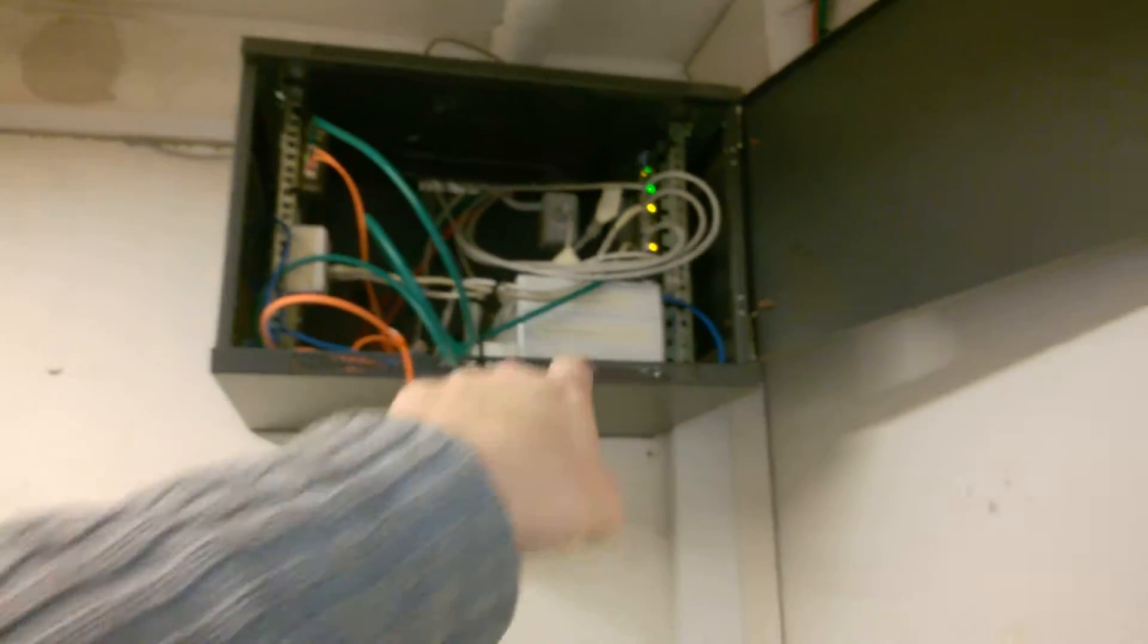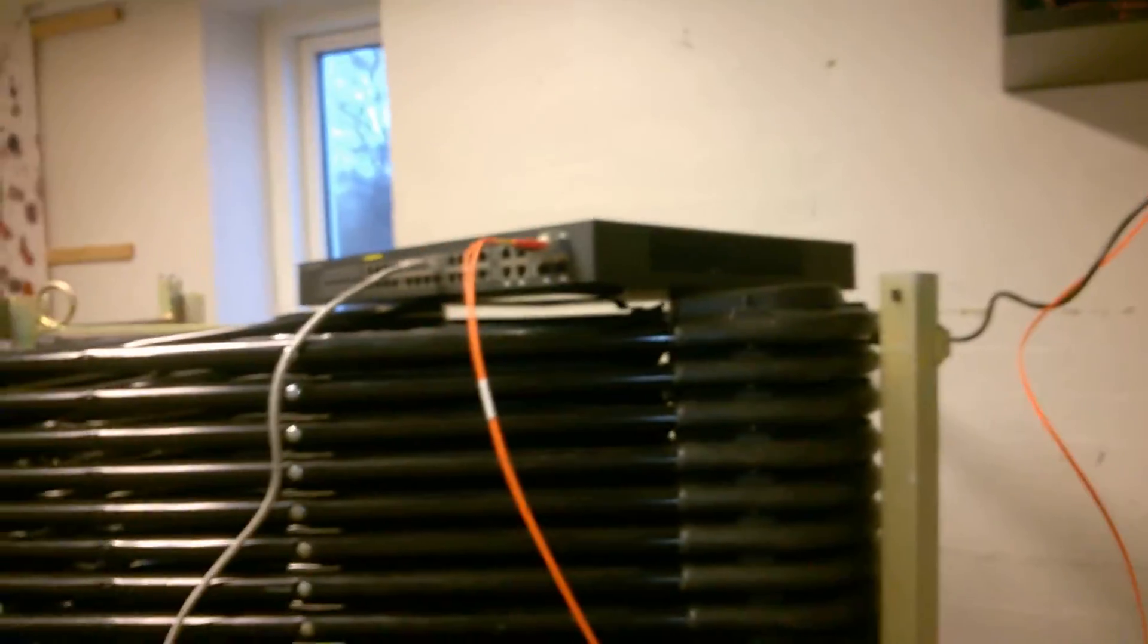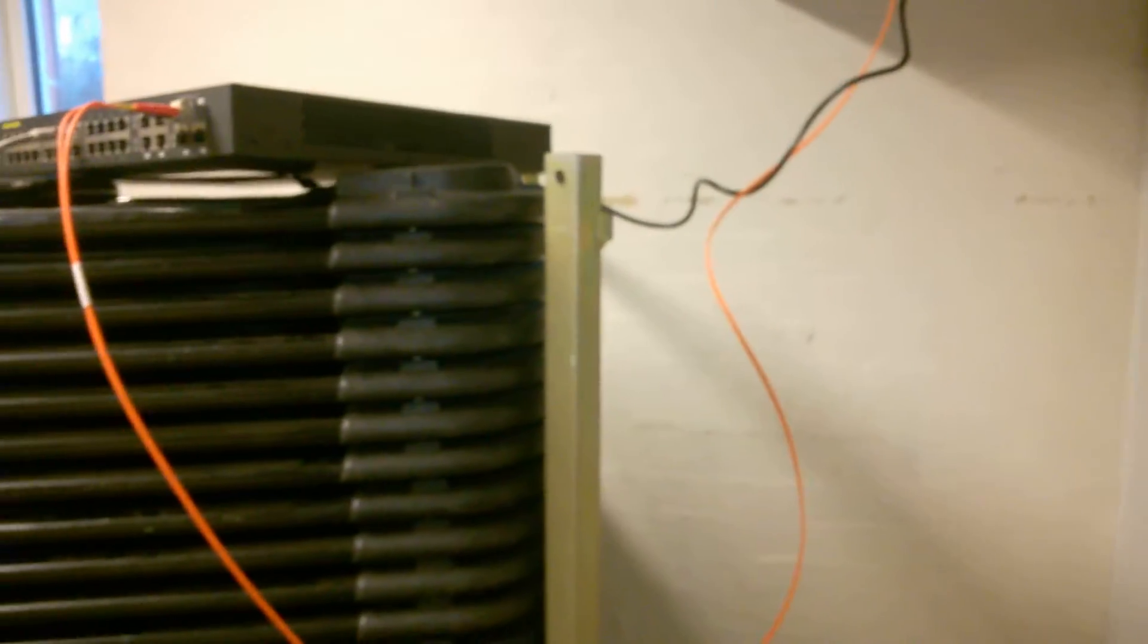It's as soon as I take out the cable from the converter, or the big box in there, and put in this cable to the switch, then it can't connect. Like there's some failure, like if you were using a single mode and then a multimode, but I'm not. I'm using a multimode and it's 62.5/125, and the old cable is 62.5/125. So I'm thinking, is there anything that I'm missing out on?